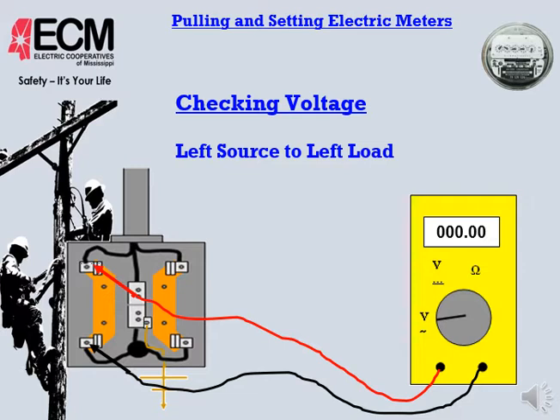If you do get voltage or some type of reading in these positions, the main thing I want to get across is that I'm not really concerned so much about where the voltage is coming from. At this point, my main concern is once we see voltage in a place where it should not be, we should hit our brakes and stop, not set the meter. And now that we've determined that we're not setting the meter, we can backtrack and try to figure out where the voltage is coming from.